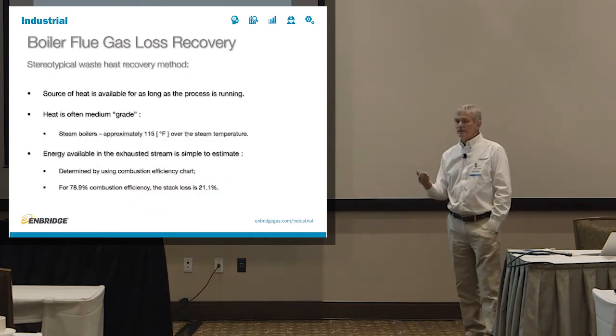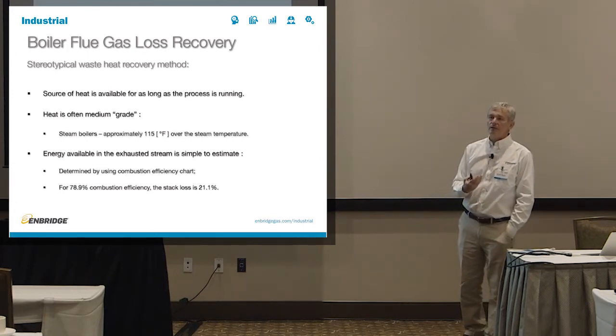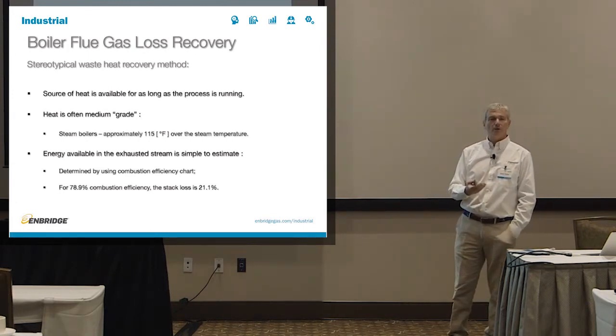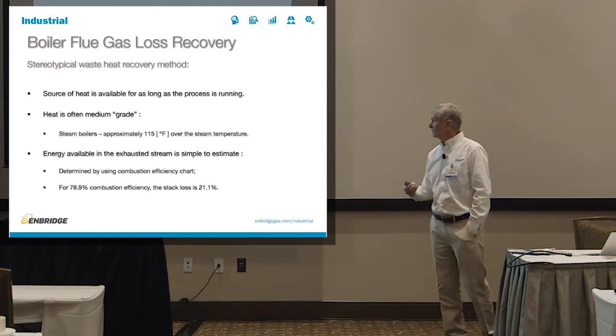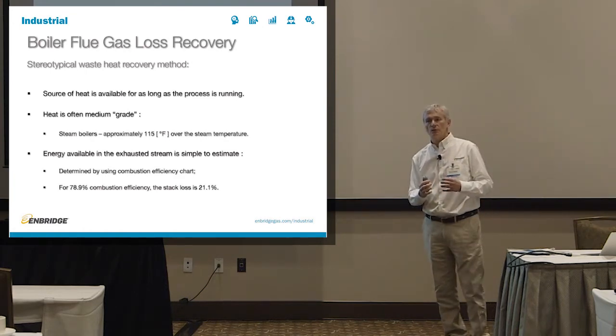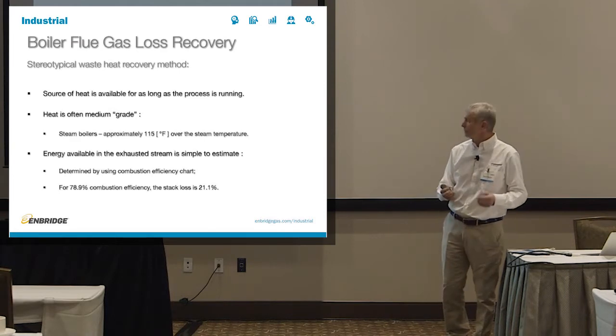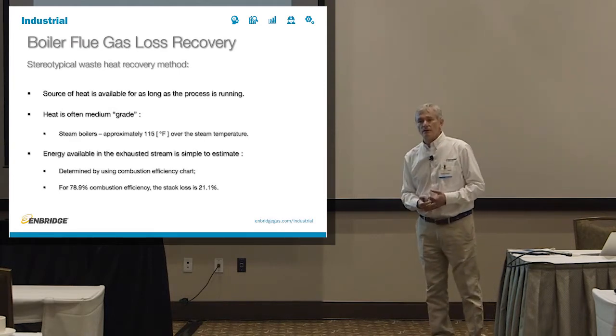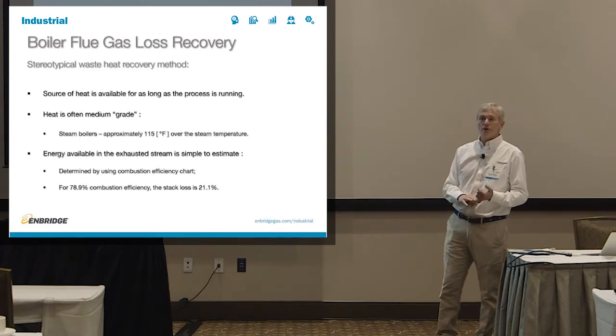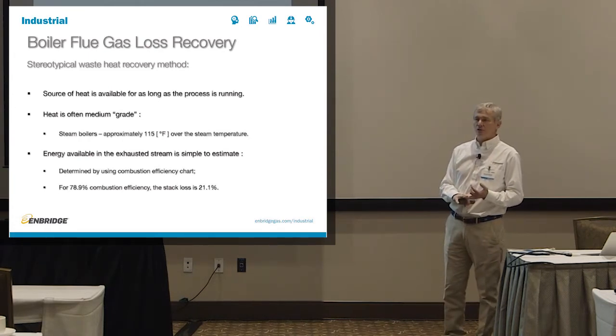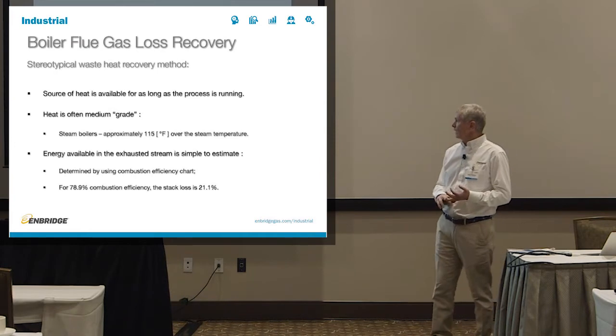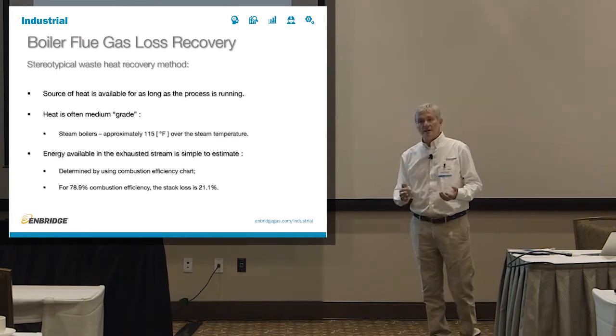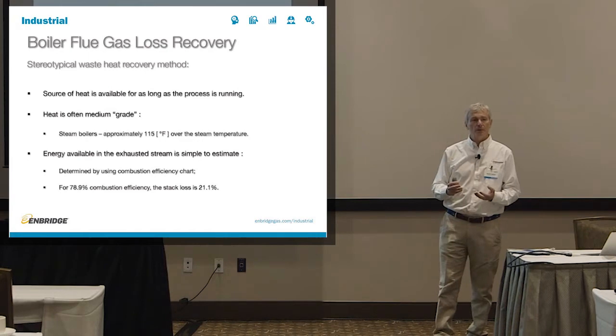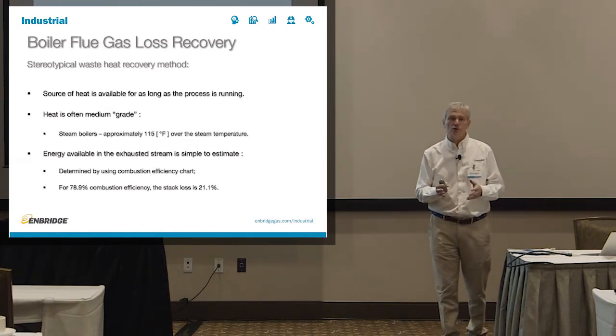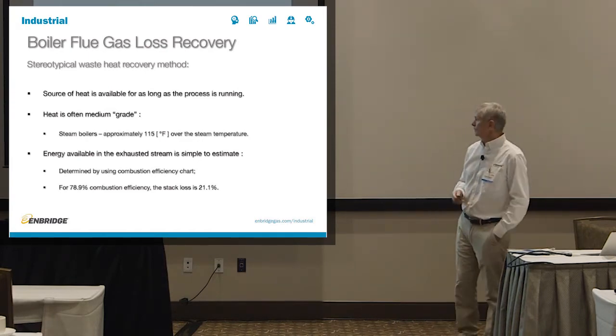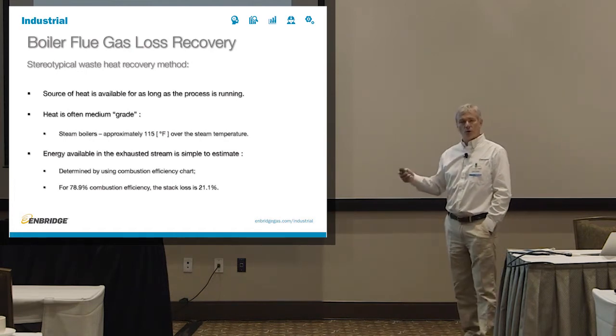So this is one of those stereotypical heat recovery methods. When you talk to people about heat recovery, that's the first thing they think of. They take the heat from the boiler's flue gas and recover it. There's good reason why that's a first thought: the heat is often medium grade. It's always there. As long as the boiler is on, the heat is there. The energy available is very easy to determine. We'll go through the example, but it's very simple to find out how much energy you actually waste in your steam boiler. A very similar approach can be taken for a hot water boiler.